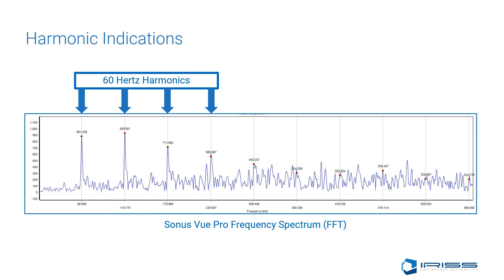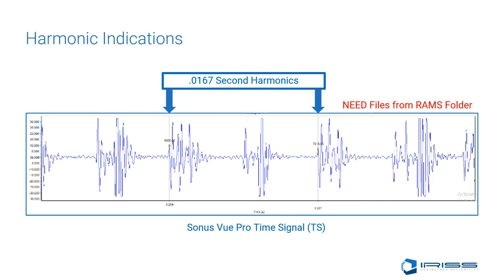Here is an example where the critical angle was achieved: around the 60 Hz mark we have the first harmonic indication, another at 120 Hz, another at 180 Hz, and a fourth around 240 Hz — then it tapers off at 300 Hz. In the first example, the inspector confirmed the correct diagnosis by identifying a 0.0167 seconds harmonic in the time signal and 60 Hz in the FFT. With clear indications in both views, the inspector can confirm achievement of the critical angle and determine the existence of treeing or tracking.